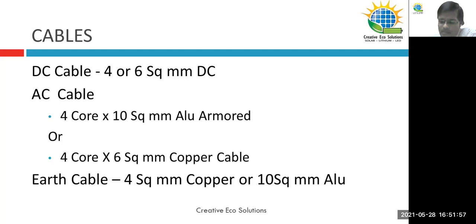And so these DC cables are UV coated, XLPO coated, so that they can withstand the heat. They will not deteriorate like your AC cable, and they can also withstand a 1000-volt DC system. Two years back, we had a 1000-volt DC cable rating. Now we have around a 1500-volt DC cable rating. So the strength is more now. And obviously, yes, DC cables are more expensive than AC cable.